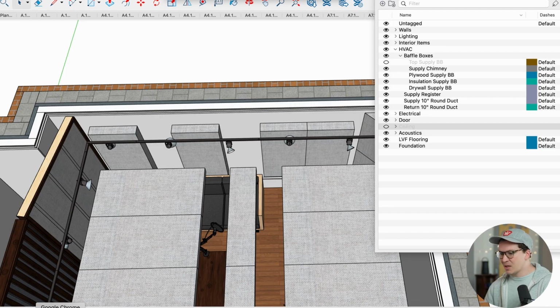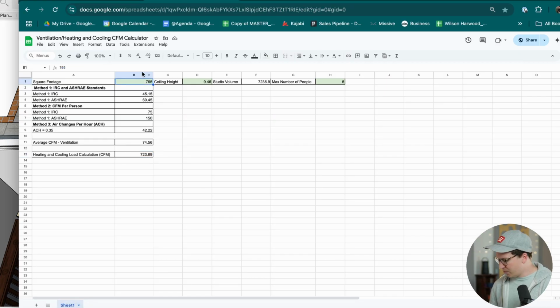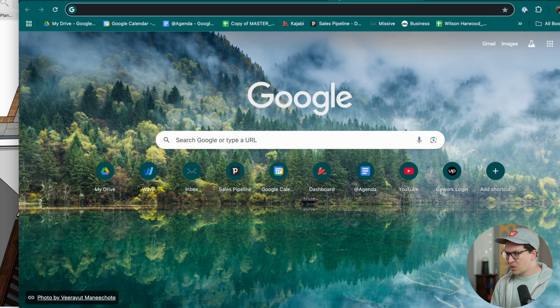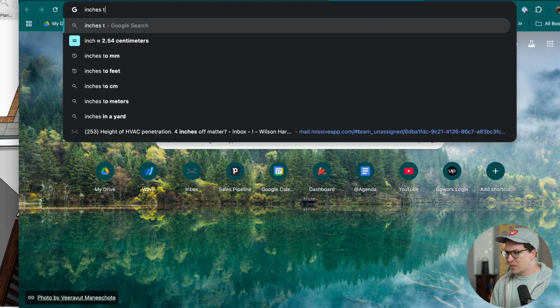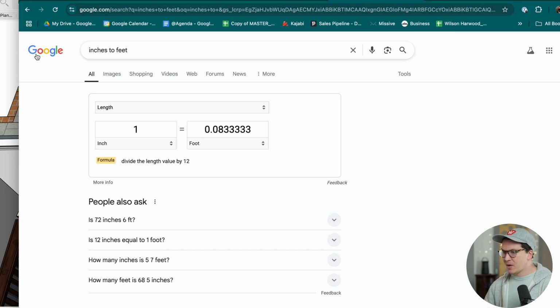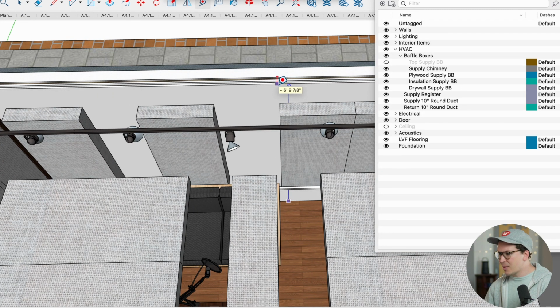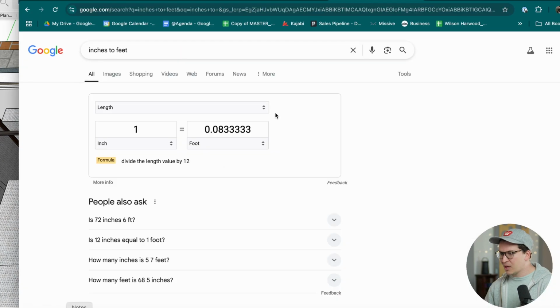221. So let's go back to this calculator here. And what we're going to do here is the square footage is 221. The ceiling height is going to be in feet. So our inches are going to have to be a decimal for this to work correctly. So what I do a lot is inches to feet. And we can go back over here and say, okay, what was our height here? 6 feet, 9 7/8. It doesn't need to be super, super accurate. So we can do 6 feet. And then the 9 here, which is going to be 0.75, super easy math. So we'll just do 6.75 in this example here. And that'll give us 149.